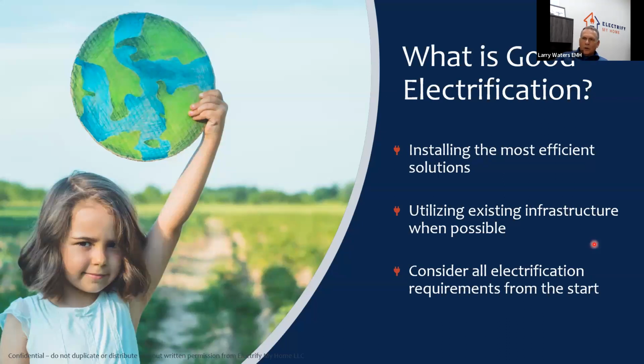But what is it? Good electrification should be part of anyone's vernacular when they're doing electrification upgrades on a house, especially with the HVAC heat pump systems. Installing the most efficient solutions should be the biggest thing that you shoot for. We install these cool little inverter heat pump systems that use a tiny bit of energy once the house is cool or warm, versus a traditional heat pump system that can take up to 6 breaker spaces and might need supplemental heating for a cold night. Those are energy guzzlers, and those are not good electrification. We try to use the existing infrastructure wherever possible. We electrify a lot of houses on 100 amp panels. We're able to do that by using low energy solutions and just smart techniques and processes around sharing circuits and things like that.